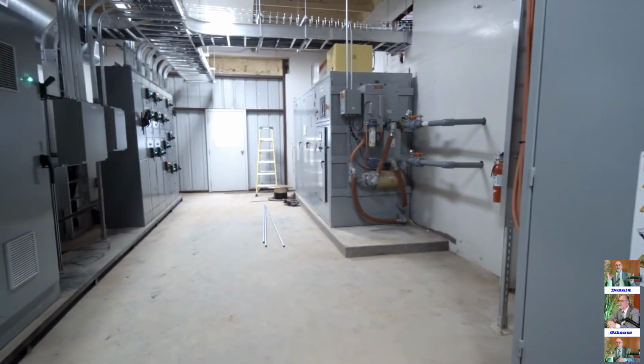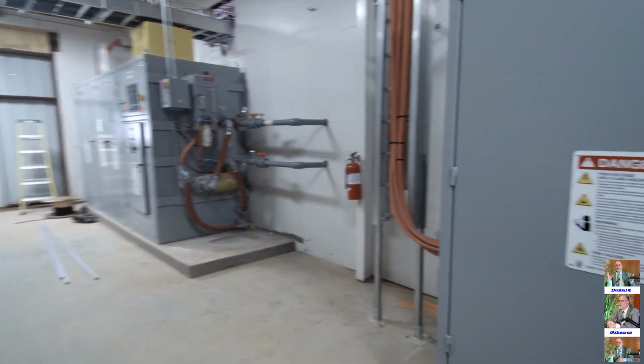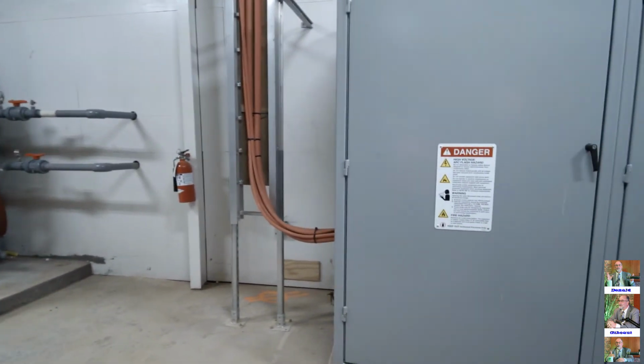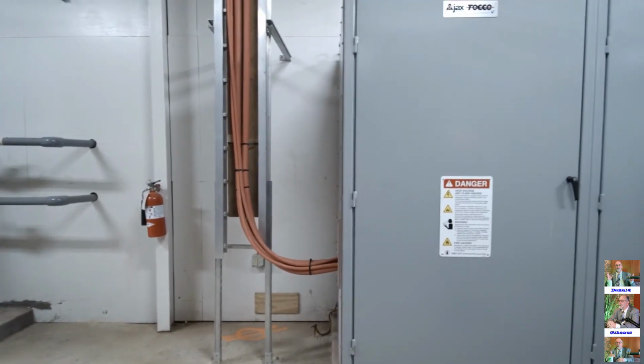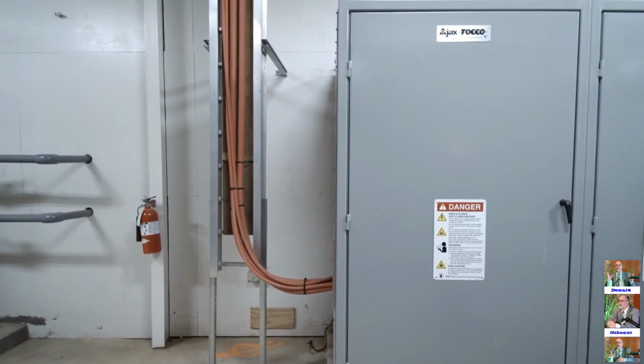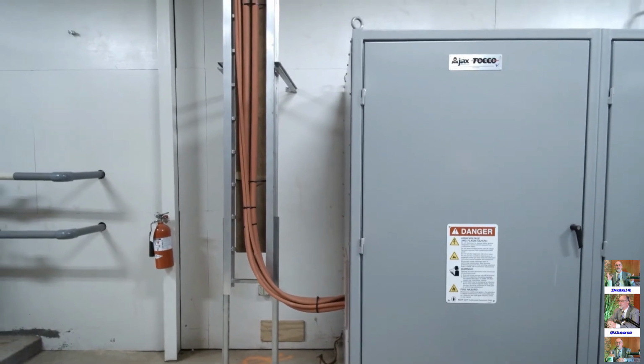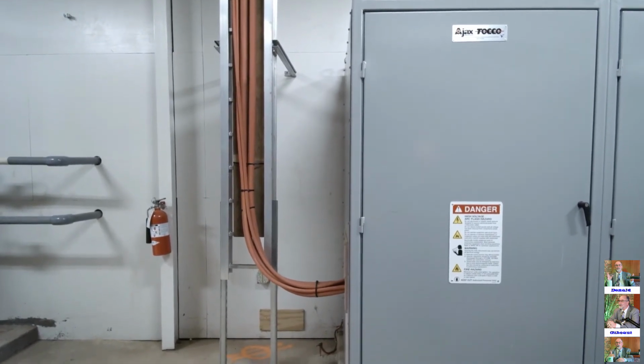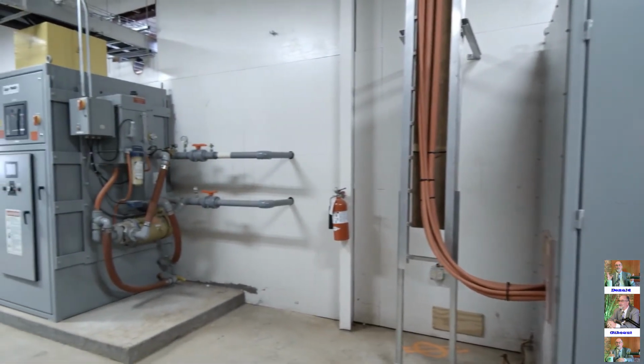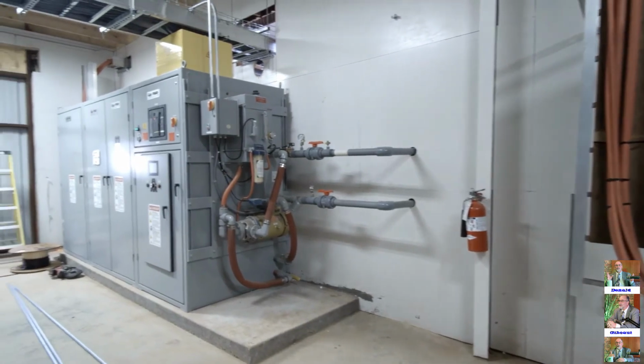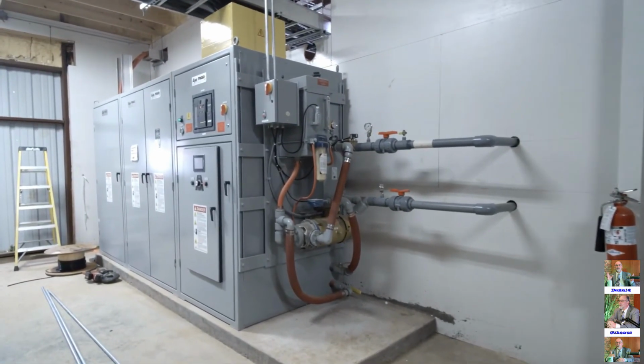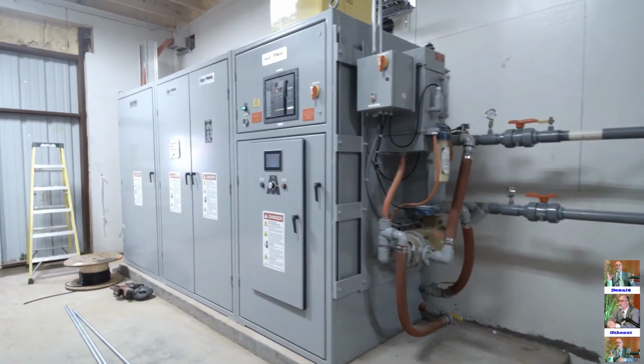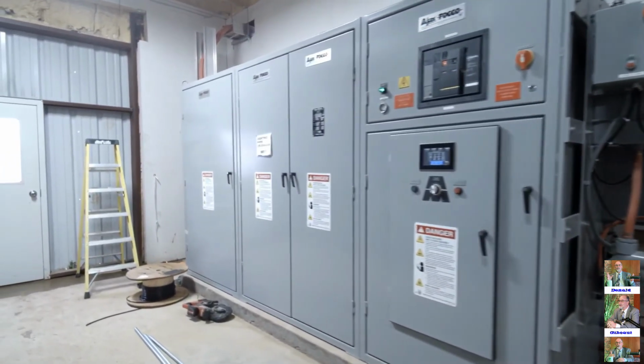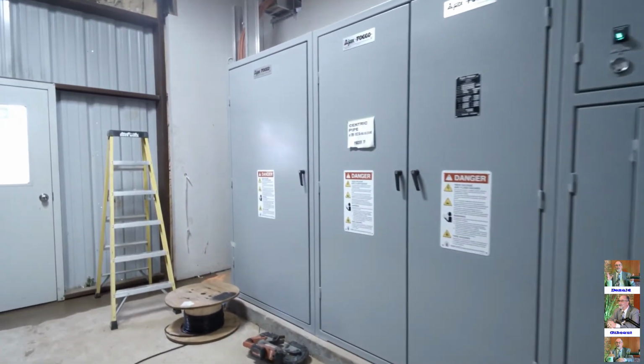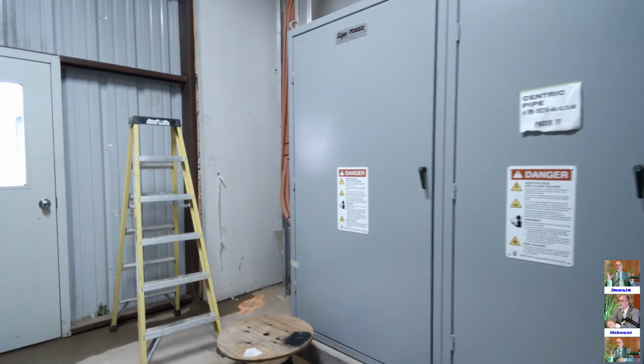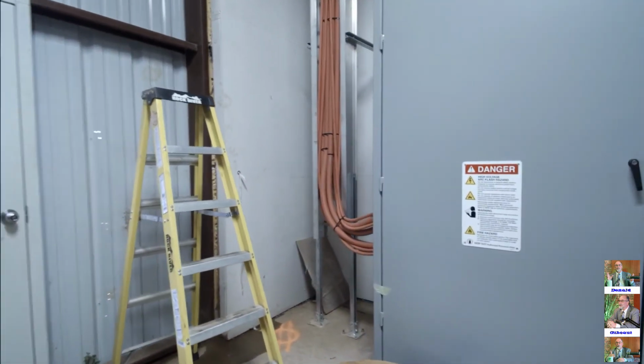This is a side mount water system that we put in and recommend on our power supplies. They're high purity water with high resistivity. Most are filled with distilled water. And it just breaks out any potential of contaminants coming through in your high dollar power supplies here that's sensitive. They have a DC section. So you have electrolysis potential across that DC section, which is basically electroplating. So we solved that issue here by putting a small water system with a plate frame heat exchanger and its own pump and reservoir and filter right at the power supply. And it's proven for a little extra money to be a great help on keeping that power supply as clean as possible.